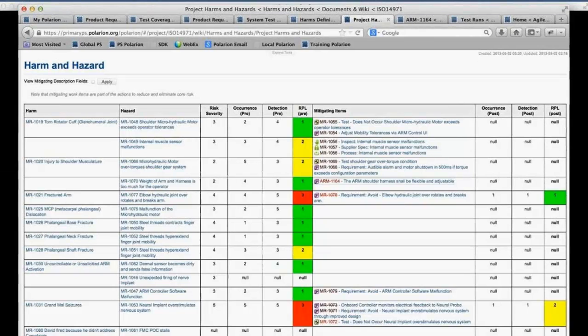And if I return back to this, I can make changes and see the completion values here of the different items. So in this page also on the right-hand side, once mitigation is complete, like you see here in this line, when the mitigating items, whether they're tests or process controls or process validation or design controls, have been fully mitigated, I'll be able to score a new value for the probability of occurrence of a particular hazard, and have a post-mitigation RPL, which ultimately can be used as part of my value to the audit process within the FDA. So our goal is to take the static value of mitigating risk and bring it back into the project, back into work items, which themselves can be actionable and managed like you do all of the other items.